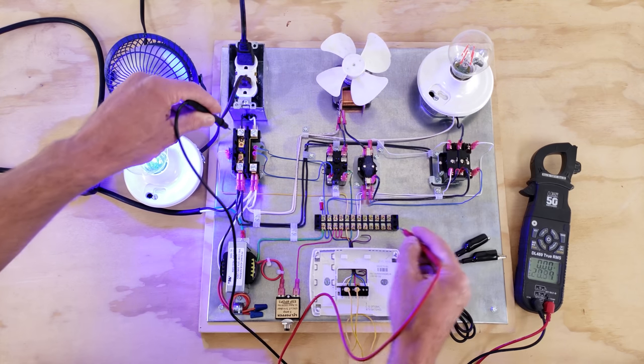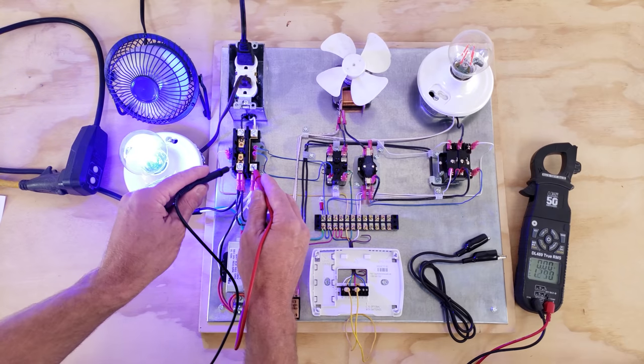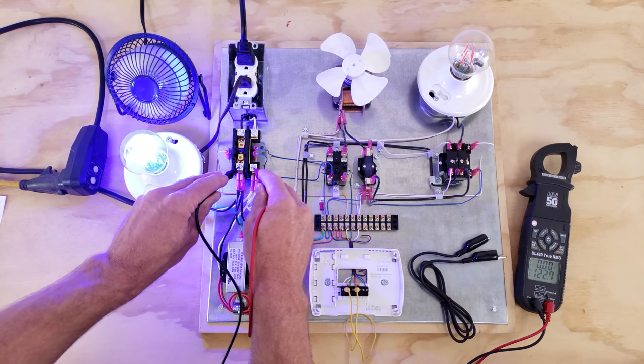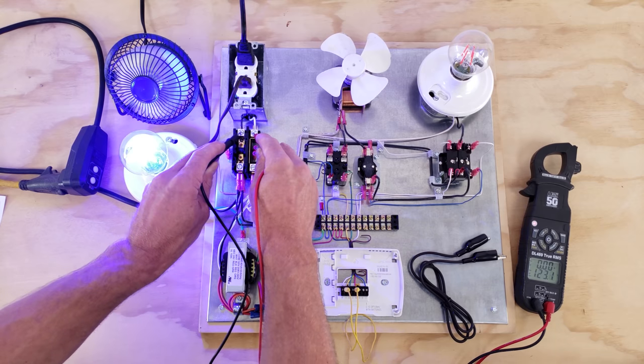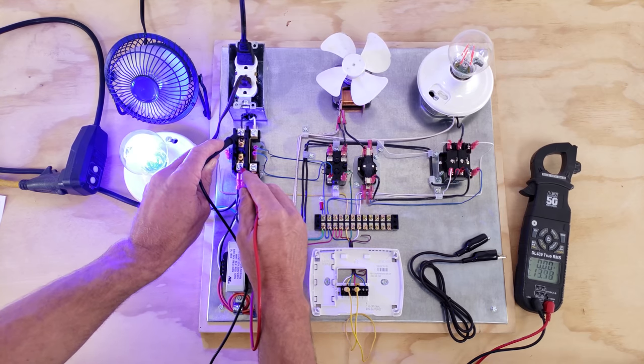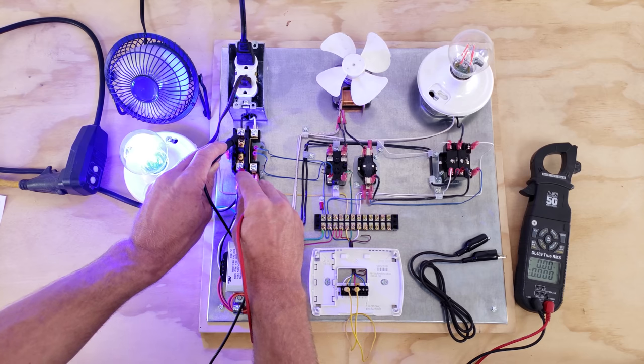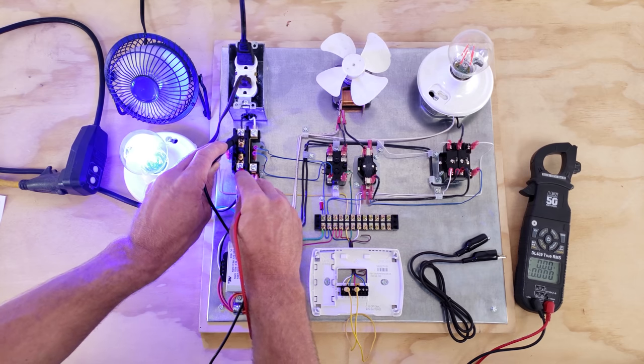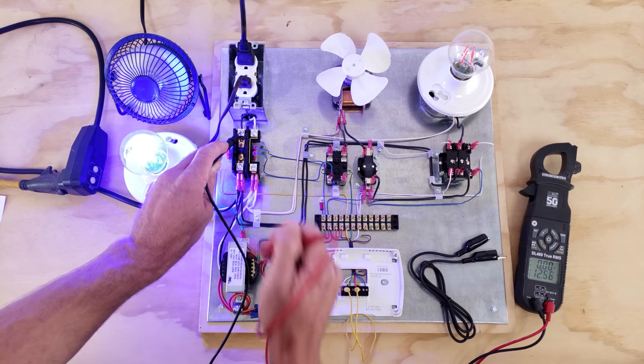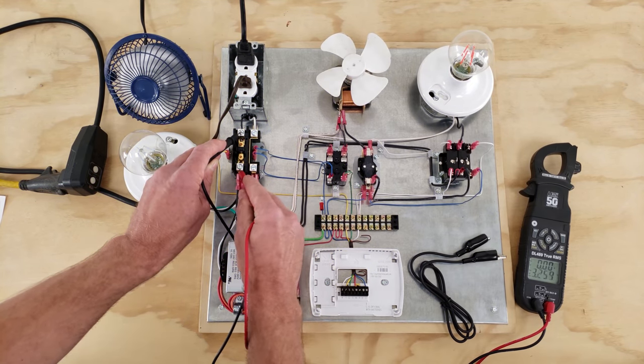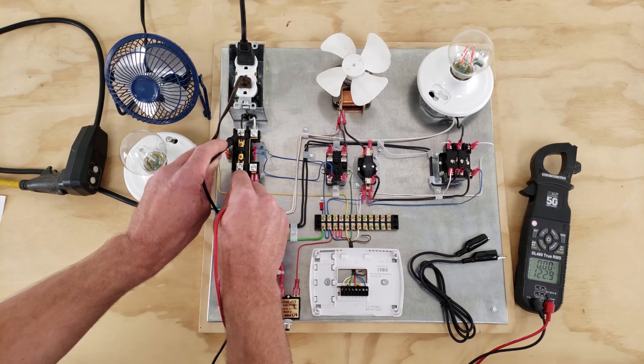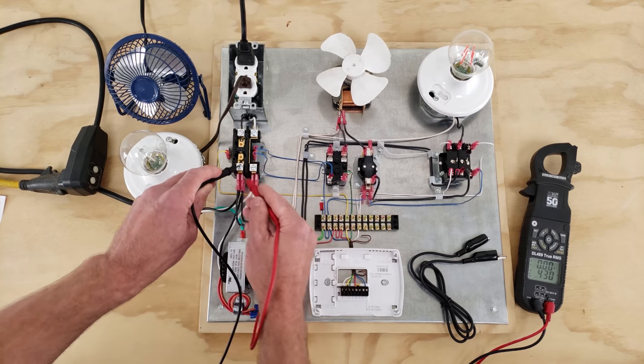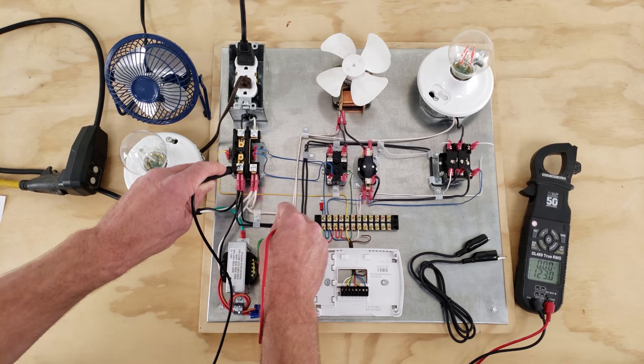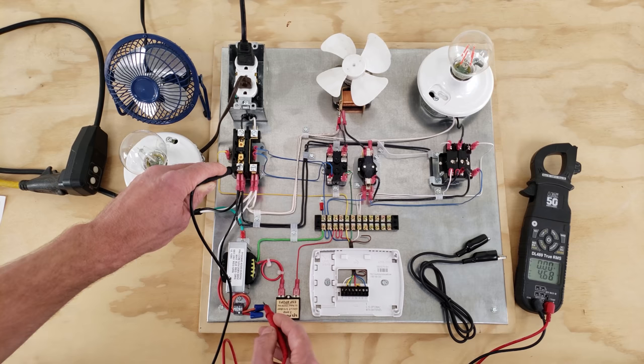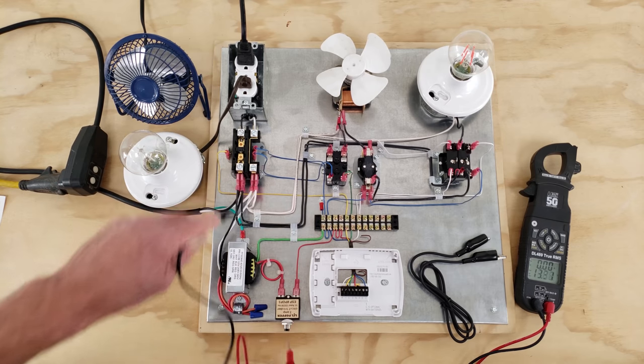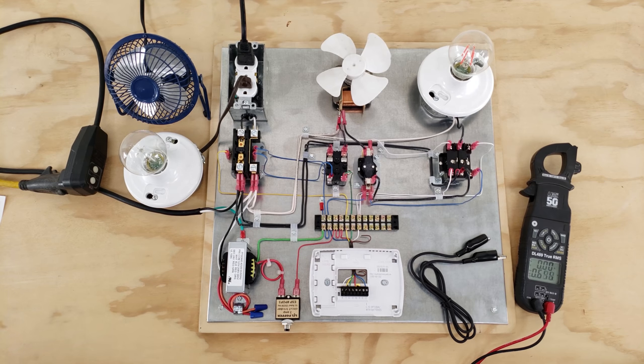And if we were to check across this switch right here, we want to measure power in. So we have power there, and we have power there. So we've confirmed that our contactor is closed. We could also take a measurement across here to see if there's any potential difference, and we see that there is zero voltage as far as a difference. If this switch was open, we would see a difference. And so you see we have 120 volts. Now, as well, we could take our hot, we can come down here onto the ground, and so you see we have 123 volts when we have our probe on hot and our ground. Now, that's only if you have a good ground on your HVAC unit, which you should have.